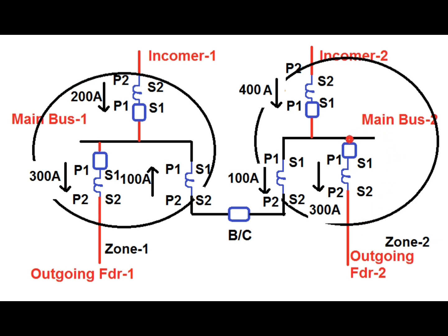Similarly for zone 2 or zone B, the load current for outgoing feeder 2 is 300 amperes flowing from P1 to P2, and 100 amperes also flows from P1 to P2 through the bus coupler. So 400 amperes flows from P1 to P2 in zone 2, while incomer 2 supplies 400 amperes flowing from P2 to P1 towards the bus. As per KCL, the sum of currents at main bus 2 is again 0, and therefore under normal load condition the zone 2 or zone B differential current is 0.